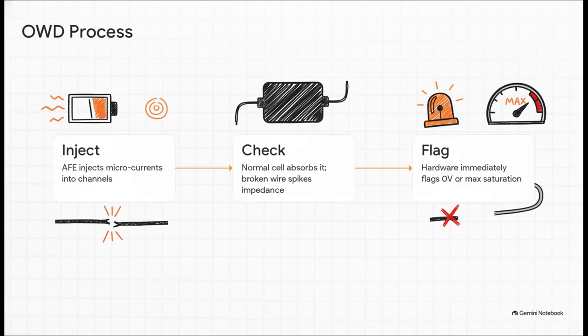In the background, it injects tiny pulses of microcurrent into the channels. If the wire is perfectly fine, the battery's massive capacitance easily absorbs this tiny current without so much as a blip. But if that wire is broken, that microcurrent has absolutely nowhere to go. The impedance spikes instantly, and the hardware flags a sudden drop to 0 volts or a max saturation, instantly catching the broken connection.